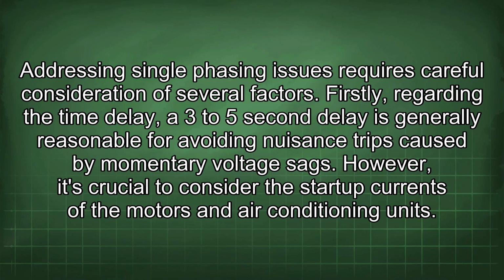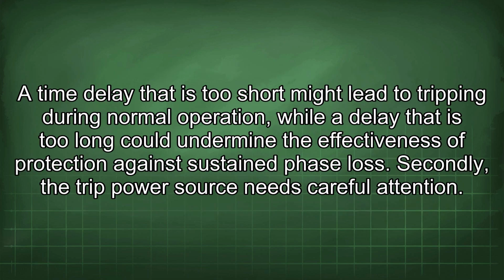Addressing single-phasing issues requires careful consideration of several factors. Firstly, regarding the time delay, a 3 to 5 second delay is generally reasonable for avoiding nuisance trips caused by momentary voltage sags. However, it's crucial to consider the startup currents of the motors and air conditioning units. A time delay that is too short might lead to tripping during normal operation, while a delay that is too long could undermine the effectiveness of protection against sustained phase loss.